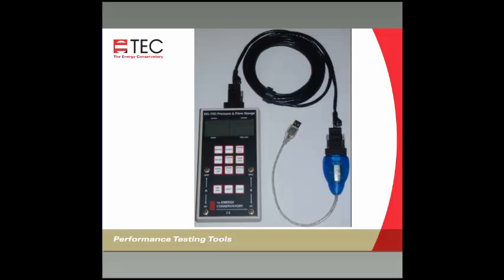I used this for a while just because it gave me, on residential testing... we have a standard straight USB cable and a port on the newer gauges, but it's still only about 15 feet long. Going with these little adapters and the USB dongle really gives you increased distance, so you don't have to worry about setting up so close to your blower door fan.